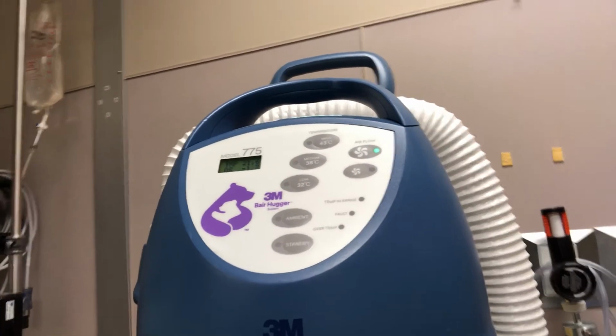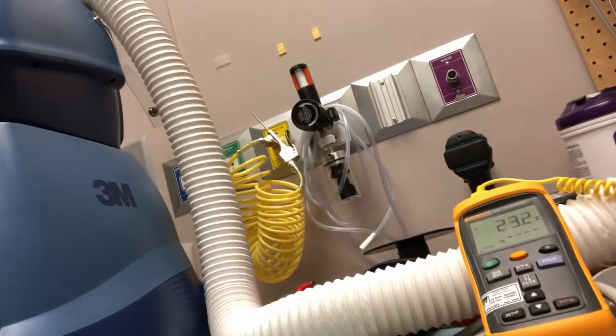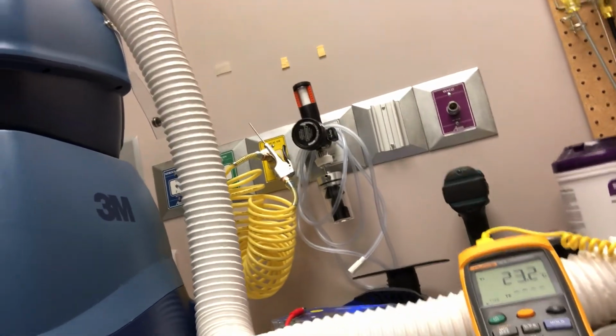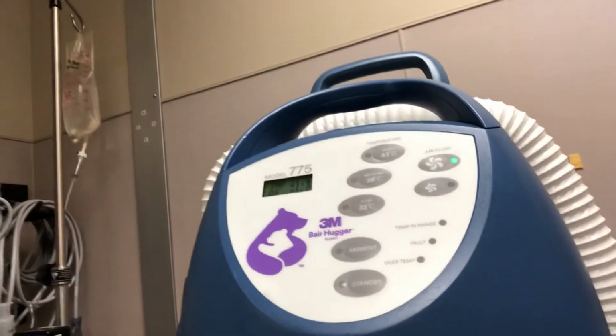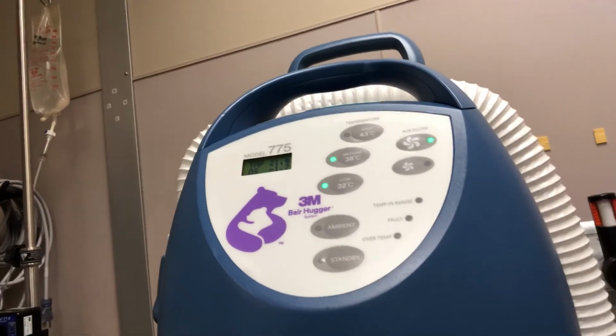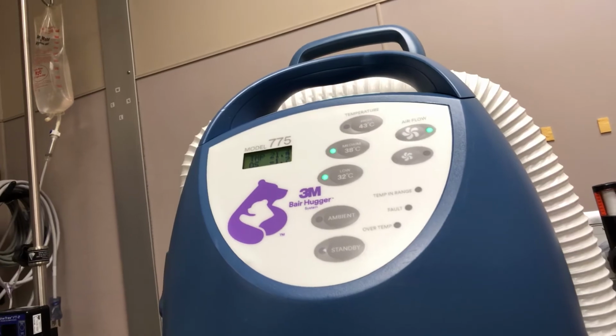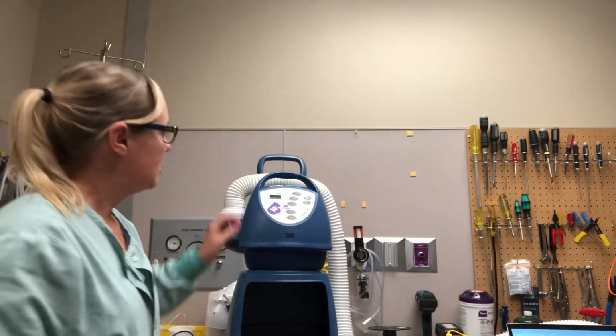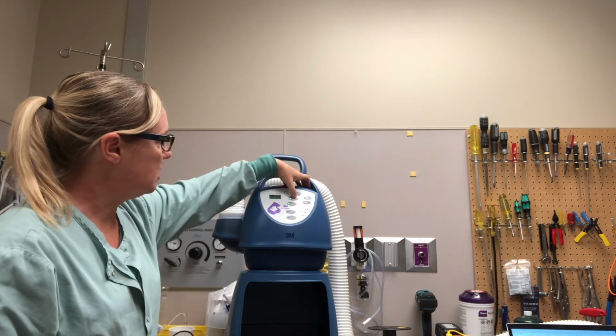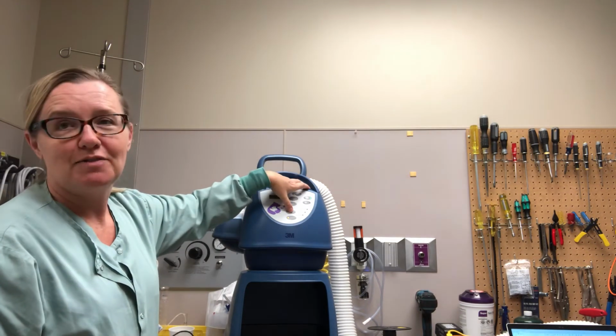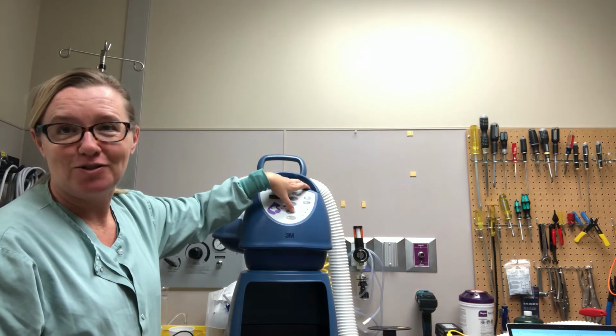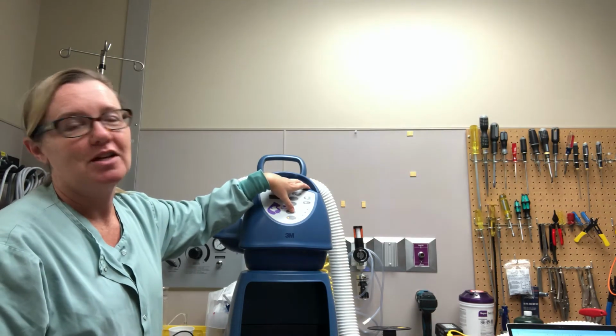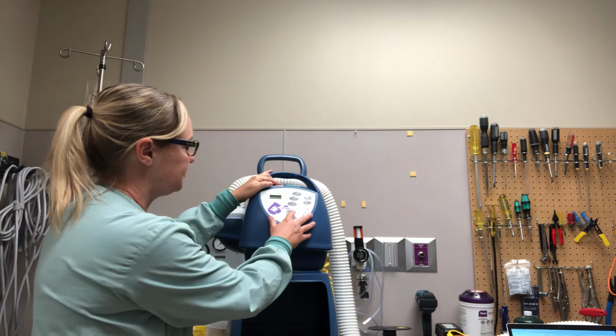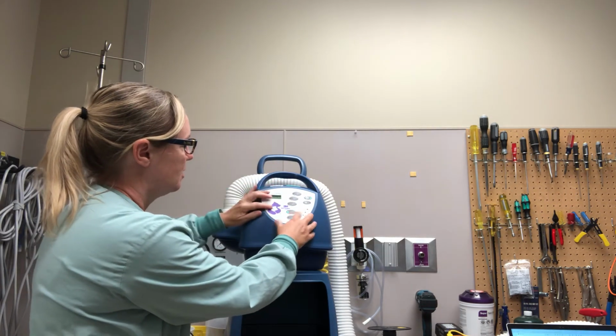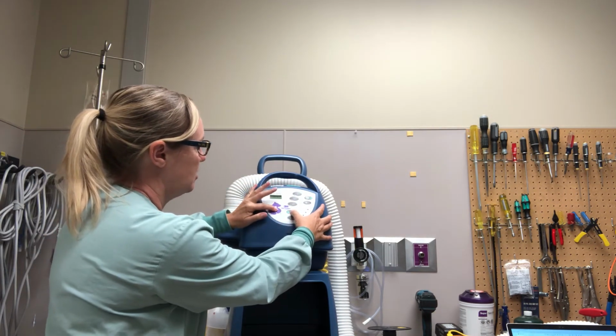So right now my thermometer is reading 23.2 degrees Celsius and we're reading 21.6 on the screen. So I'm going to go ahead and increase this by pressing, and that's a safety feature, it just shut off because I was taking too long in the service menu. So I'm going to restart and get back into my service mode.